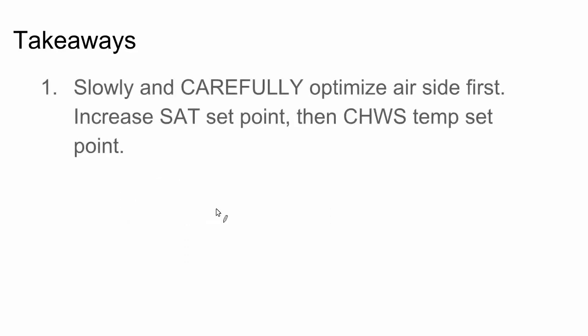So what are the takeaways here? Well there's three points that we talked about. The first is that you want to optimize the air side first. And you do that by carefully increasing the supply air temperature set point, and then and only then making a permanent change to the chilled water supply temperature set point. Always observing and checking to make sure the changes you're making are not impacting comfort or performance anywhere in the building.